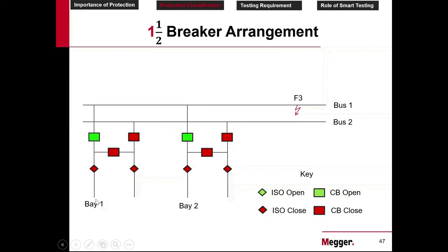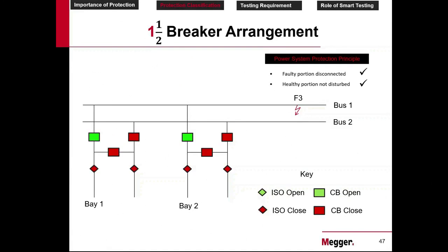When you trip this, you can find that there is another path through which the supply is already flowing. That means there is a very short duration of disturbance. The duration of disturbance is going to be in terms of milliseconds because the breaker operation time is in milliseconds. Typically a breaker operates in 40 to 50 milliseconds. Even if you assume the worst case, double the time, 100 milliseconds, we should be able to trip these 2 breakers and clear the fault. So you can see here, earlier we took 40 minutes, but now we took only 100 milliseconds to satisfy this protection principle. Therefore, the 1.5 breaker arrangement is one of the superior category.